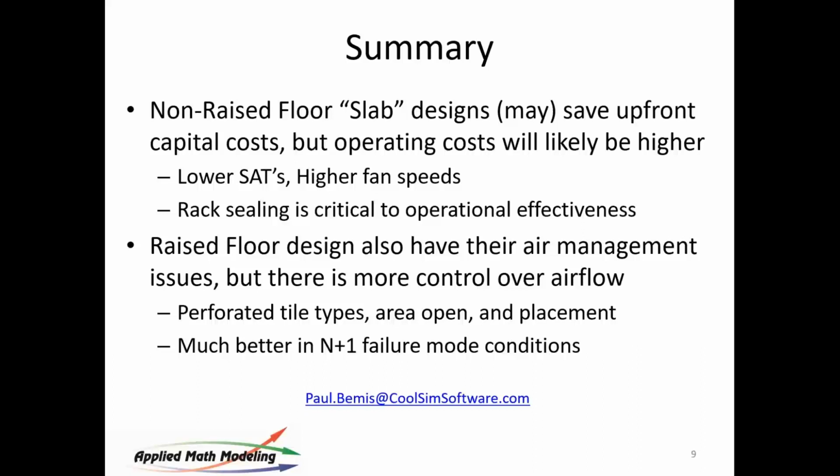Unfortunately, many people use that to turn them on full. They just turn them on full speed and override the thermal management system so they have no hotspots. But there's only a certain amount of air in the room, and if you pull too much in places you don't need it, it's going to sacrifice it for the rest of the room.